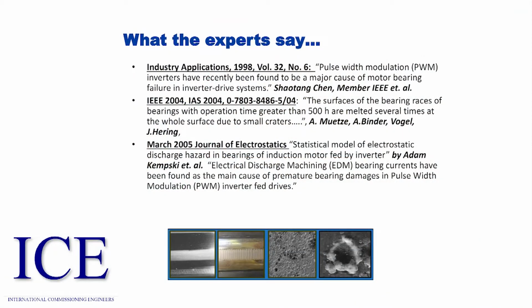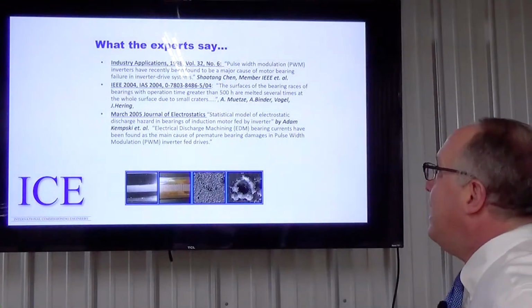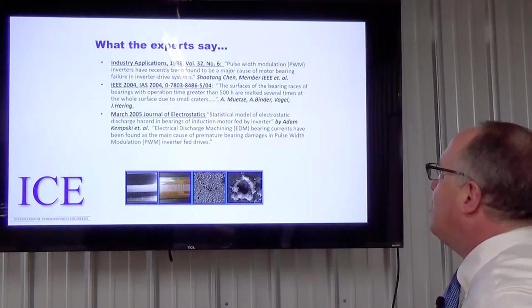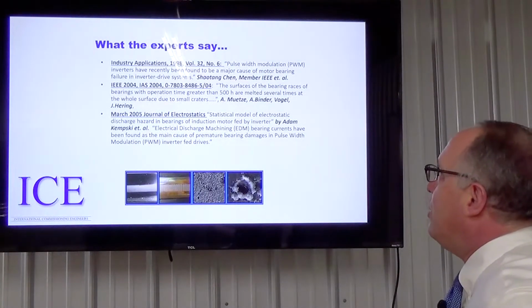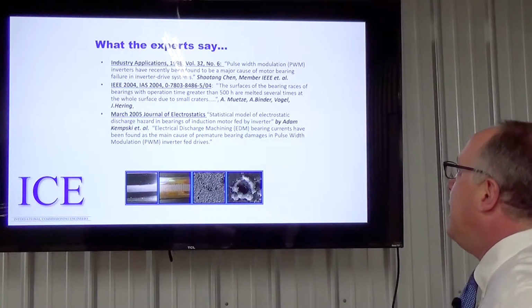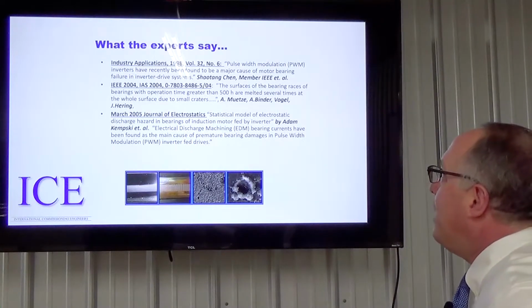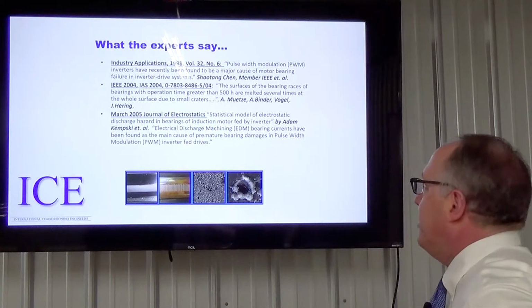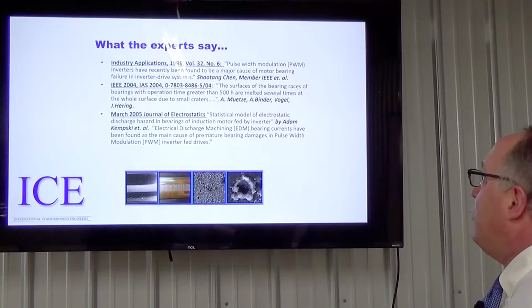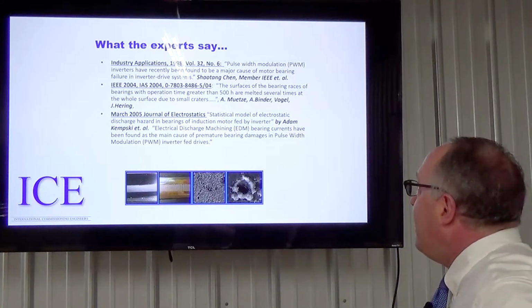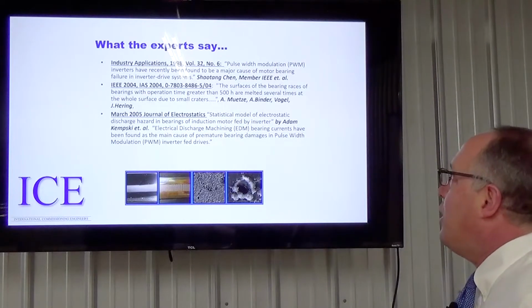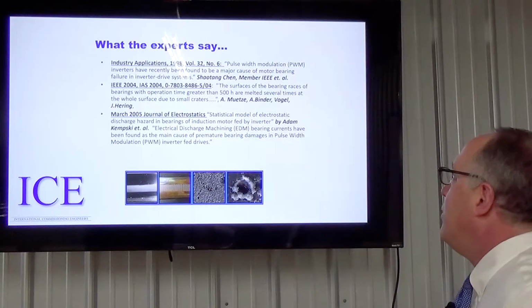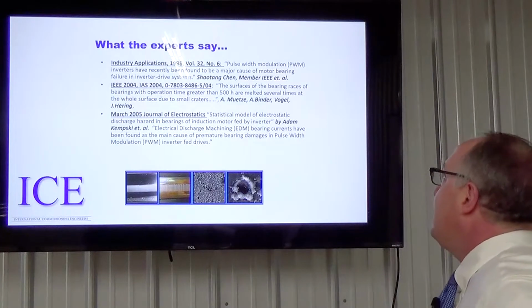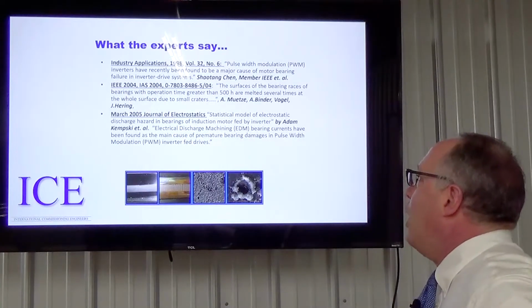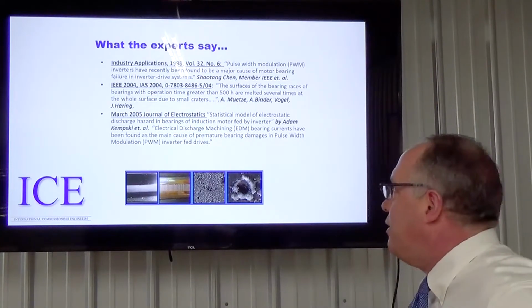What do the experts say concerning this? Well, Industry Applications said that pulse width modulation inverters have recently been found to be a major cause of motor bearing failure in inverter drive systems. The surface of bearing races with operation greater than 500 hours are melted several times at the whole surface due to small craters.